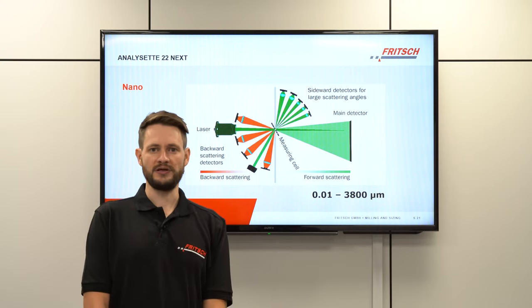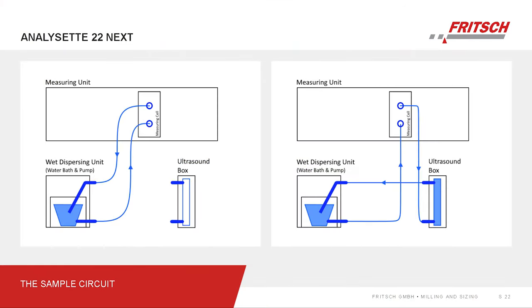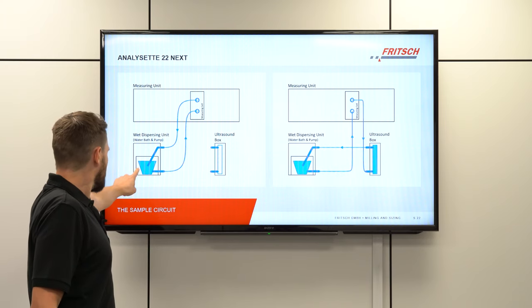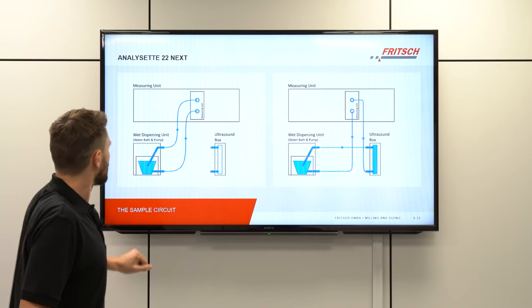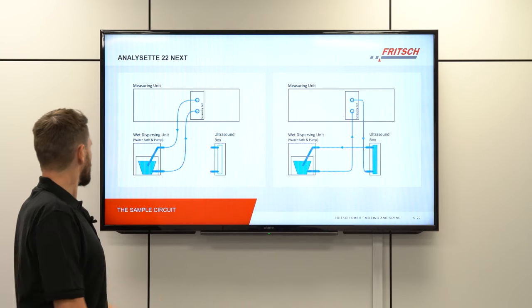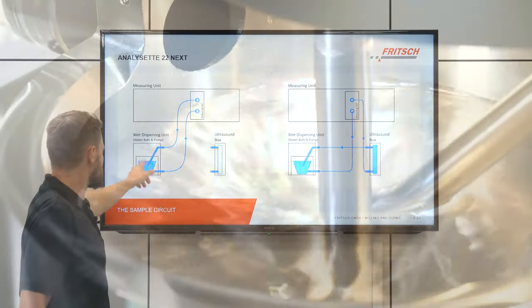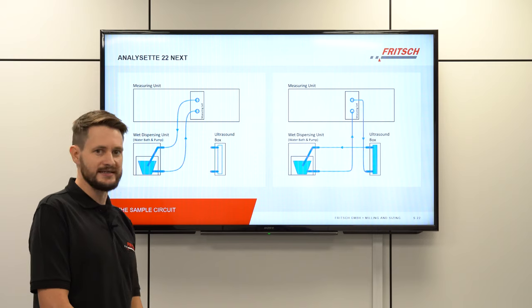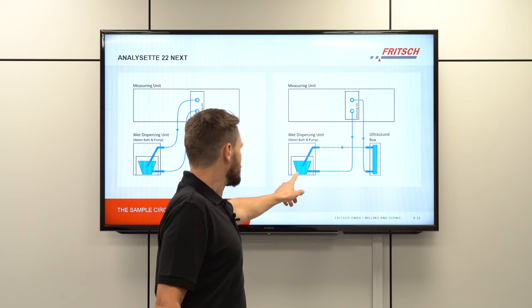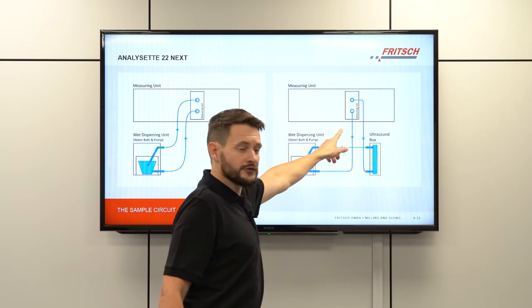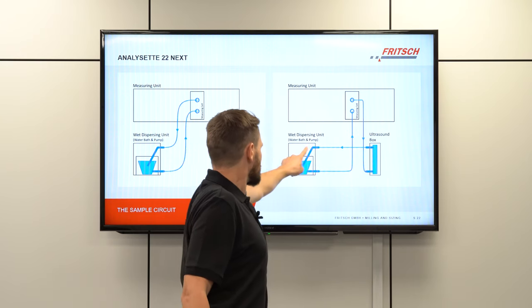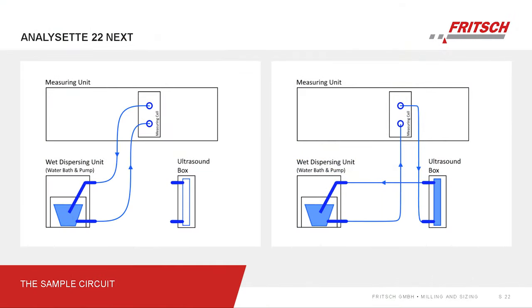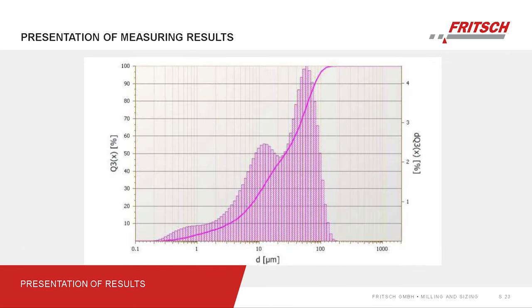For sample circulation within the system there are two possibilities. In the first method, the wet dispersion unit has a chamber with a water bath, and the water is pumped through the measuring cell and back into the water bath through a pipe — the so-called reflux, whose position can be changed depending on the application. If ultrasound is needed for a sample, you can connect the hoses so the water flow also passes through the ultrasonic box before returning to the water bath.